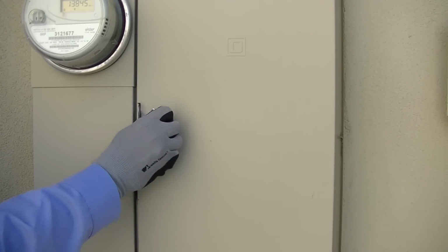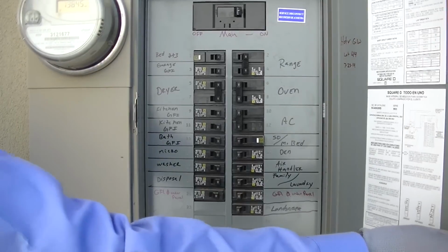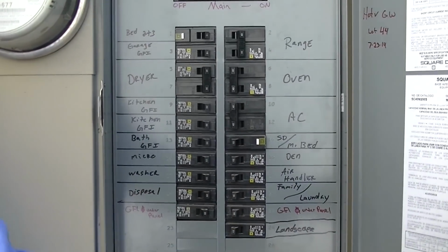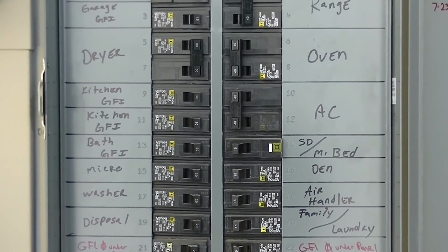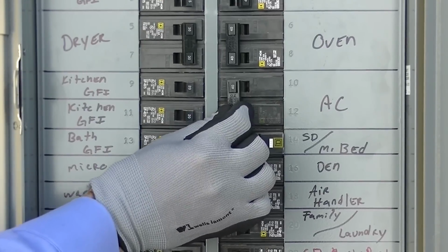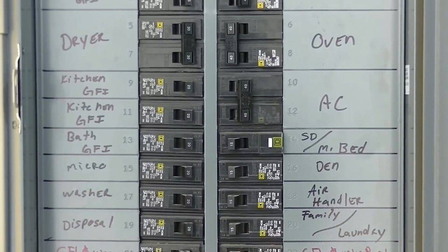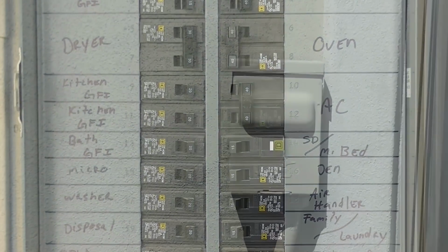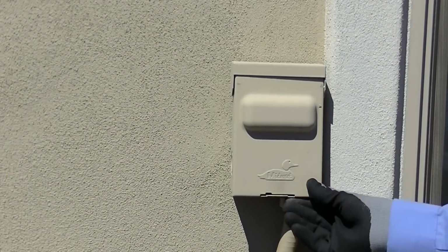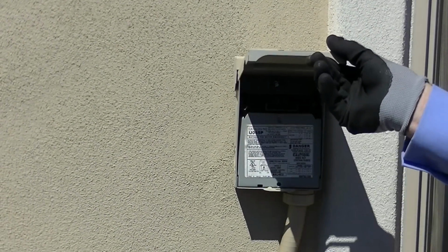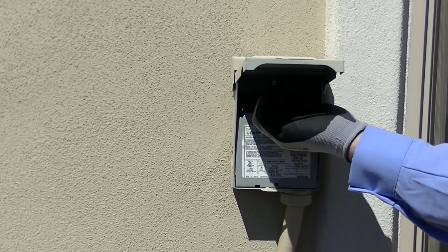Today we're going to show you how to install your new contactor. To prevent any shock hazards, the first thing we need to do is go to our circuit breaker panel, find the circuit breaker labeled AC and switch it into the off position.